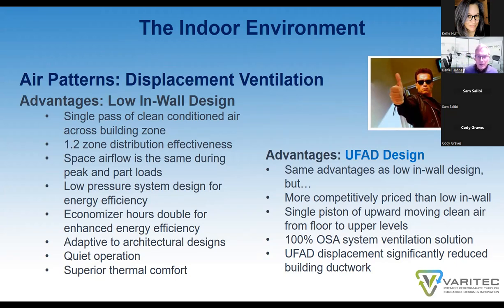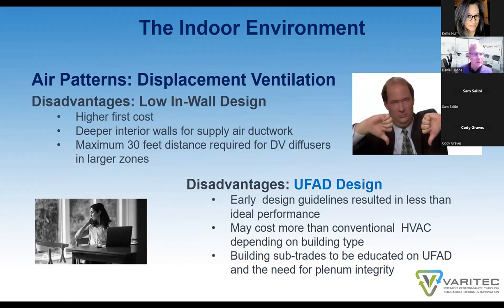The advantages of an underfloor displacement design are the same as the low in wall design, except they are more competitively priced than low in wall solutions. They offer a more effective piston of clean air being drawn from the floor up across breathing zones. We can provide 100% outside air UFAD systems, which is a very compelling design strategy, and UFAD systems radically reduce the amount of ductwork in a building, something that architectural design teams can find very attractive.